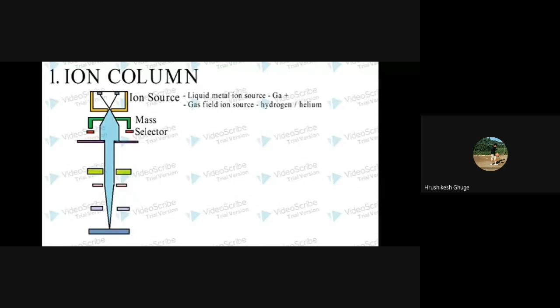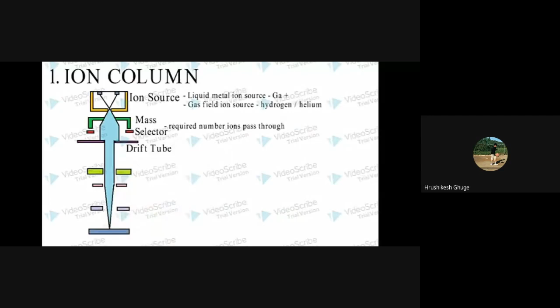The next important part is the mass selector. It is a setup that allows only the required ions with a fixed mass-to-charge ratio to pass through it for the machining process. Then there is an aperture or a drift tube which allows only the atoms which are traveling in a vertical direction. Then there is a set of lenses, out of which the condenser lens controls the diameter of the ion beam. That is, it can increase the size of the ion beam.